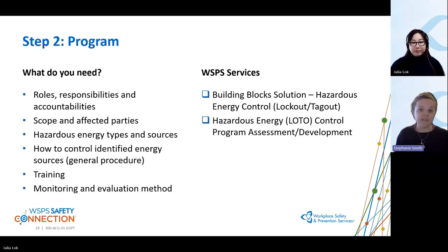It may include some general knowledge about how to lock out an electrical source versus pneumatic, but it's not equipment specific. Oftentimes the program itself makes way for specific procedures, and says how those procedures will get done. As Rob said, the knowledgeable person is the one signing off on the program and the procedures. When we look at procedures specifically, that's looking at a specific piece of equipment and how you would lock that down. What are the steps to lock out that specific equipment, and where are your energy isolation devices?